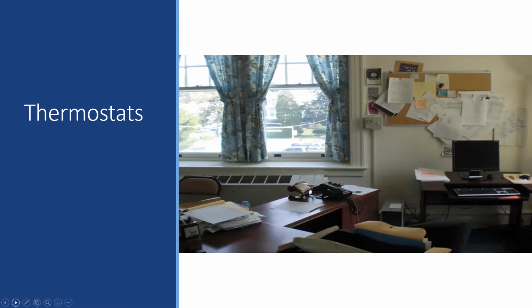In this picture, we can see that the thermostat is not only next to a window, which would be cold in the winter time, it is next to a heat source and is immediately above a computer, which would also be exhausting heat. In addition to all of that, it is on an exterior wall. This room has very limited opportunity to be as comfortable as expected when using that thermostat. These are things to keep in mind as you consider installing new equipment or upgrading new equipment, or just understanding how efficient your equipment can be in the setting that it is.